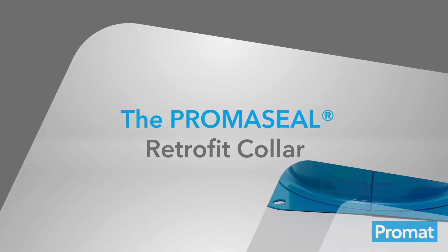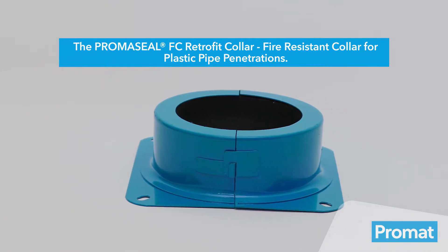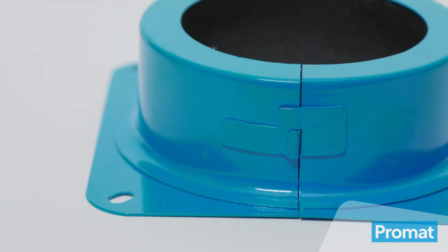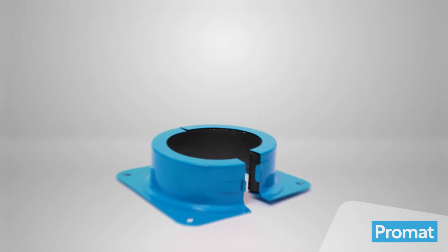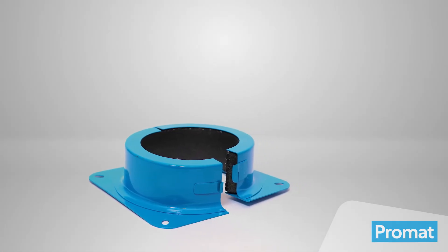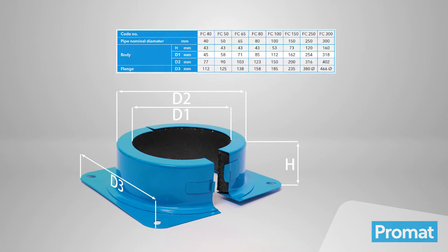The PromaSeal Retrofit Collar is a multi-purpose collar designed for use with concrete slabs, masonry and lightweight walls and lined ceilings. This split type collar has a simple clip and hinge system that allows it to be retrofitted when necessary, and is available in a range of sizes to suit plastic pipes of an outside diameter up to 315 mm.